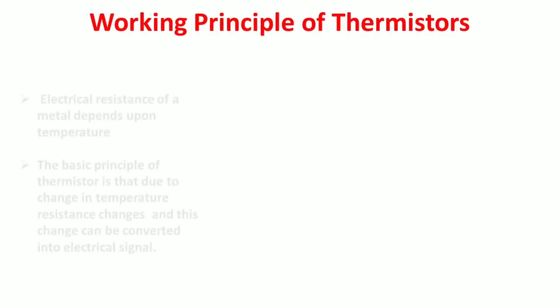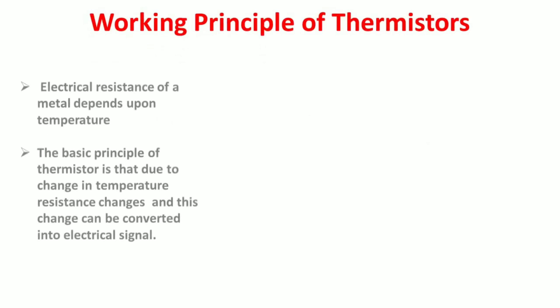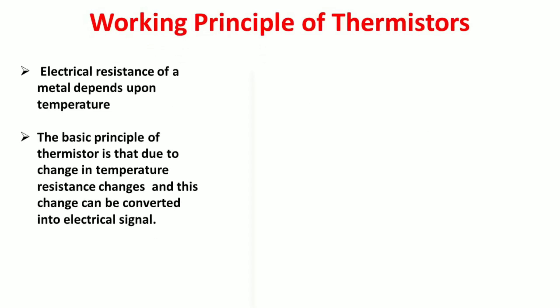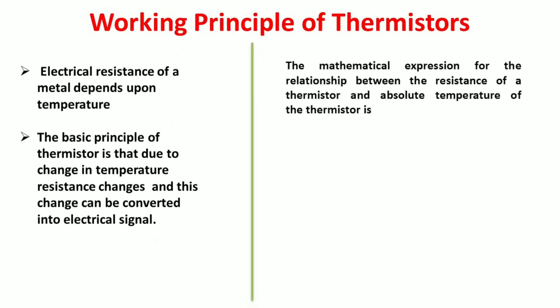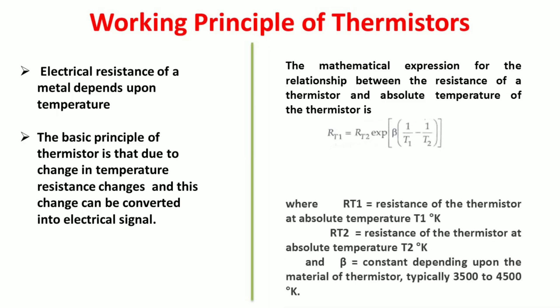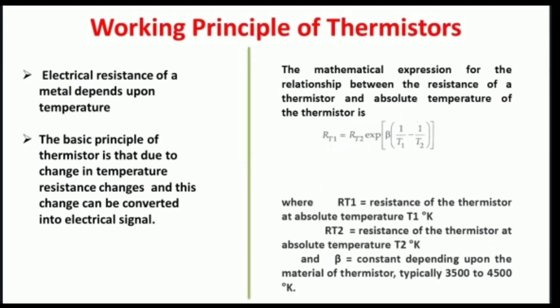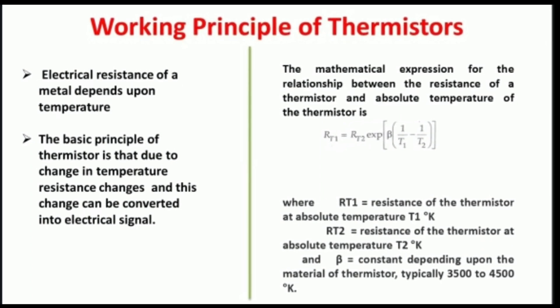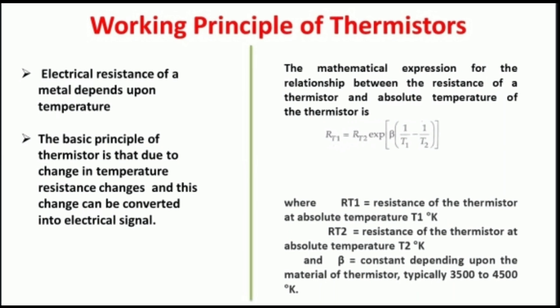Moving on to the next slide, that is principle. Thermistors are based on the principle that due to change in temperature, resistance of a metal changes. Mathematically we can express the relationship between resistance and temperature as: RT1 equals RT2 times e to the power beta times 1 by T1 minus 1 by T2. RT1 is the resistance of the thermistor at absolute temperature T1 degree Kelvin. RT2 is the resistance of the thermistor at temperature T2. Beta is the constant depending upon the material of thermistor. Its value ranges from 3500 to 4500.